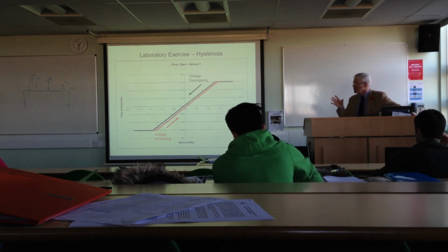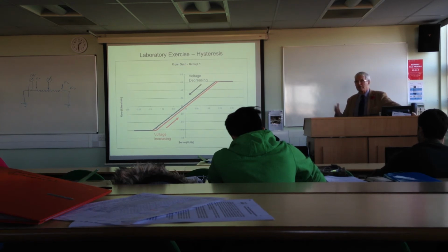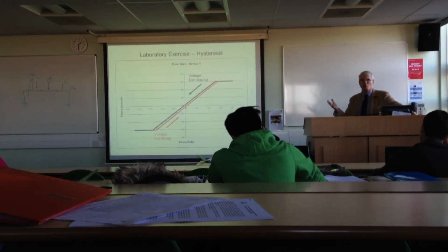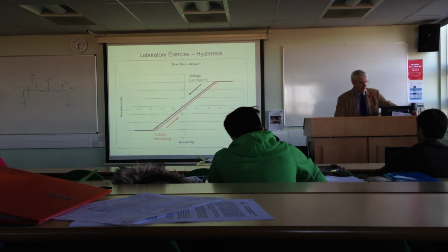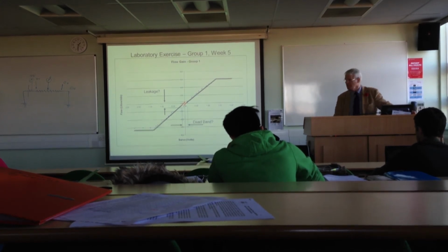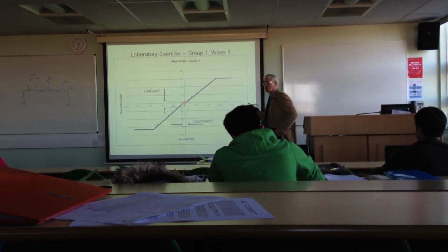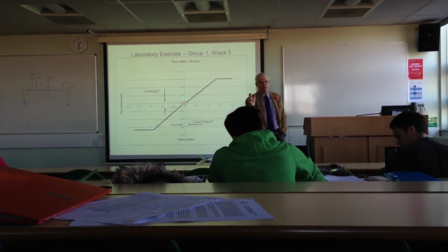So what I'm suggesting is when you look at your results, you don't necessarily have to draw one line and come up with one result. But I've given you a few explanations as to what the valve might be doing and what actually might happen. Let's just go back to this one. Yeah. I think I suggested with this one that this valve, if it had an overlap on it, would give us something like that.